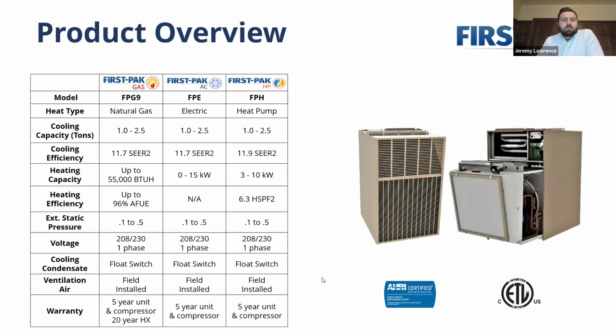The First-Pak units, these are the high efficiency gas systems, 95%. There are gas systems, there are air conditioning only with electric heat, and then there is a low ambient heat pump with electric heat as well. These systems are a smaller, wider cabinet. They were built, in fact, to compete in that Magic Pack and Napoleon condo pack market. So that's the sleeve size that they fit, and they're completely modular. So if the air conditioning system was to fail, just slide it out, slide a new one in, and the unit's up and running again.